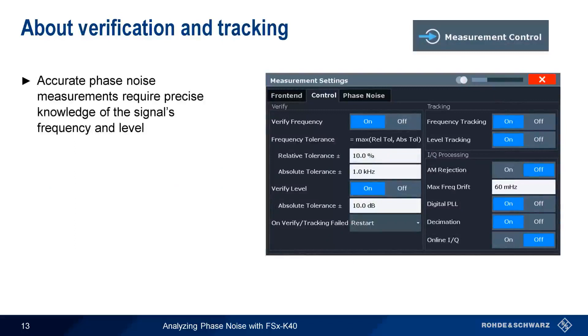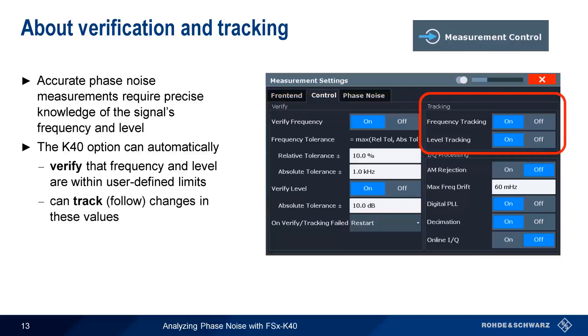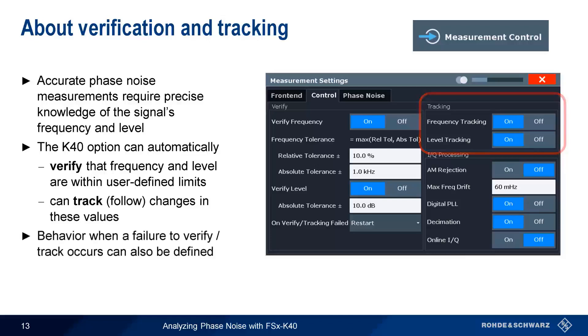In order to accurately measure the phase noise of a device under test, the analyzer requires precise knowledge of both the frequency and the level of the signal. The K40 option can automatically verify that the signal's frequency and level are within user-defined limits. If necessary, it can also track these values — that is, automatically adjust settings to compensate for small variations — which is particularly useful for devices that tend to drift, such as voltage-controlled oscillators. If verification or tracking fail, a user-defined action can be taken, such as running an auto-leveling routine, restarting, or stopping the measurement.